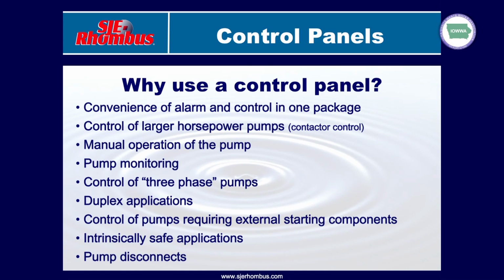Duplex applications, and when I talk duplex, I'm talking two pumps where you alternate between the two pumps. We don't have the ability to do that and get even usage out of the pumps with just a pump switch. So with a control panel, we can have an alternating circuit inside the panel. It gives us even wear and tear on both pumps. External start and run components or cap kits for the pumps are going to require that we use a control panel if that's the type of pump you're using.